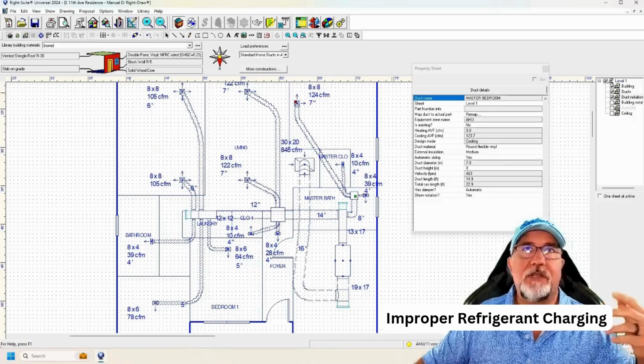The next thing that's a big issue is the refrigerant charge. Now, charging refrigerant. Let's go back over here to our picture. This is just a quick mock-up of your refrigeration gauges going into the units on the low pressure and high pressure sides to charge the system. The manufacturer comes with its own guidelines. It says, based on so many feet of refrigerant, there is subcool and superheat, depending on how you're charging the system. Also, weighing the amount of refrigerant that goes into the system is very important.